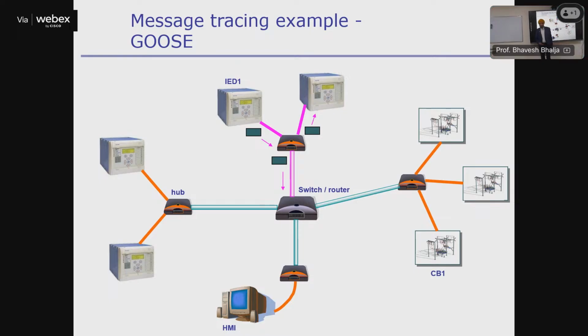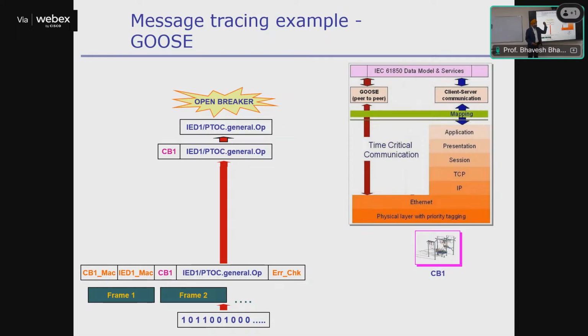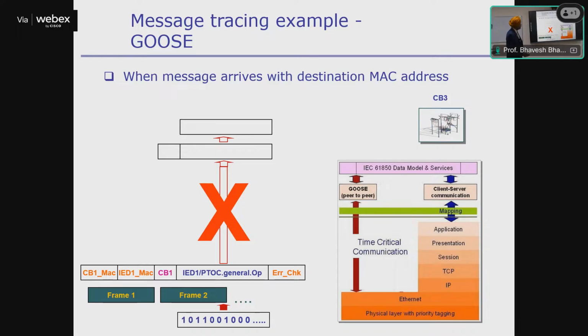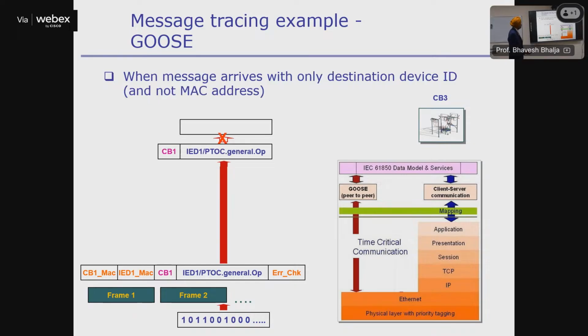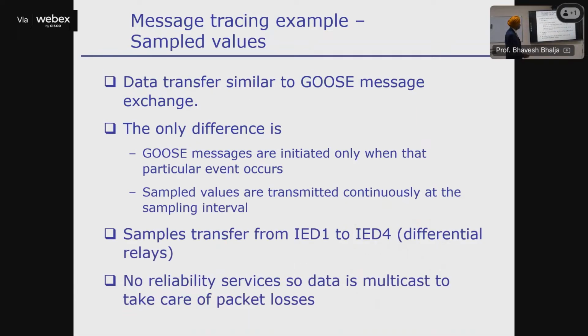Eventually circuit breaker 1 is going to recognize that it's for it, because it has its MAC address. So then it's going to strip that information and know that it's to open that circuit breaker - that protection is meant to open that. So this is how the circuit breaker will be opened. Depending on how you set it up for recognition, sometimes they have the MAC address, sometimes they may have only the destination device ID, but that's how it happens.